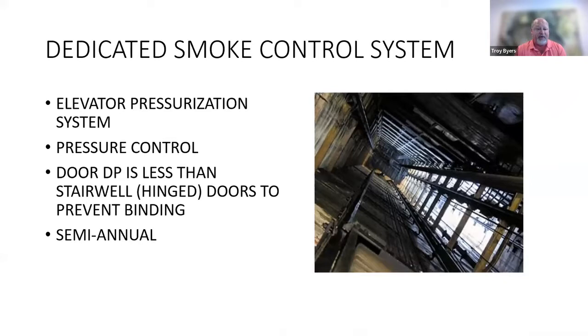When we get into an elevator shaft pressurization system, again, you're going to have some means of pressure control. The door DP requirements are typically less than what we see in the stairwell. In your stairwell, we're talking about a hinged door, but in the elevator it's more of a curtain door, and pressure on those doors could cause some binding as they're trying to slide, right? So in the elevator, we typically see 0.10 to 0.25 as opposed to 0.15 to 0.35.